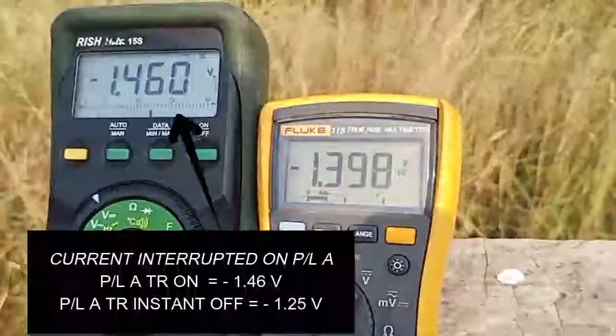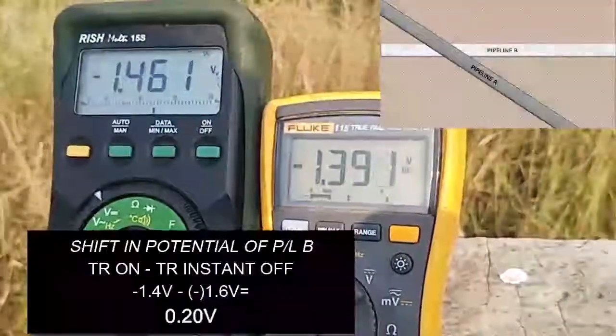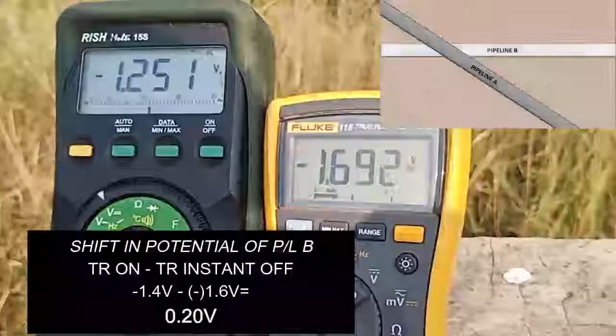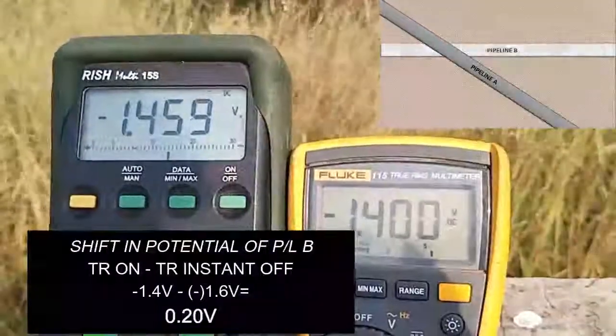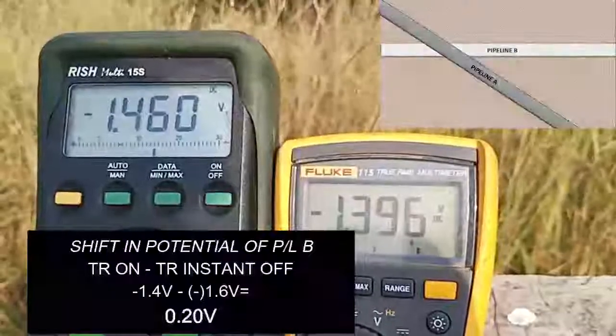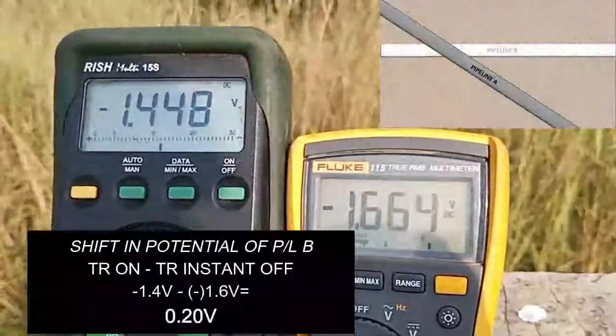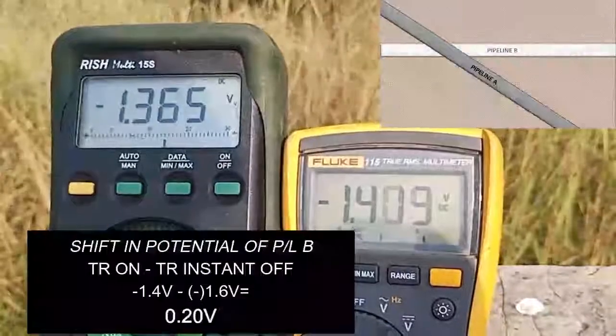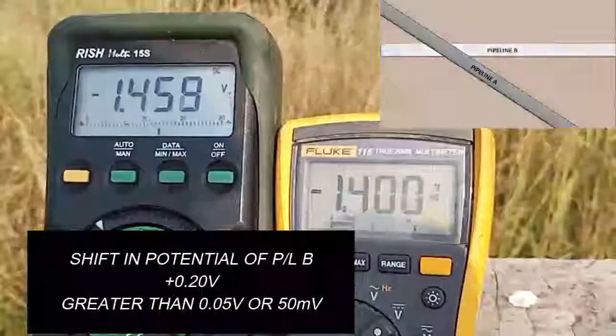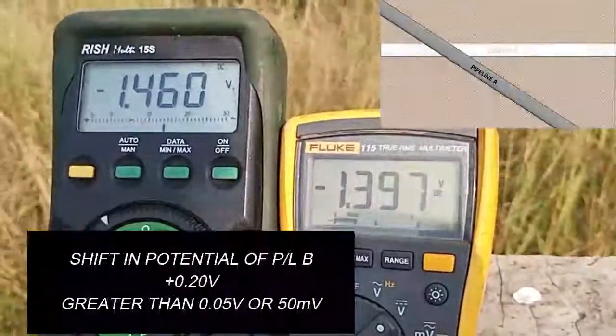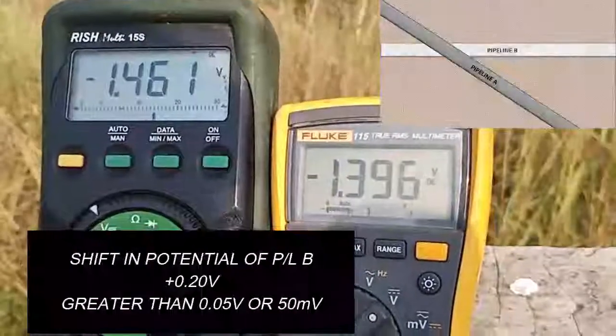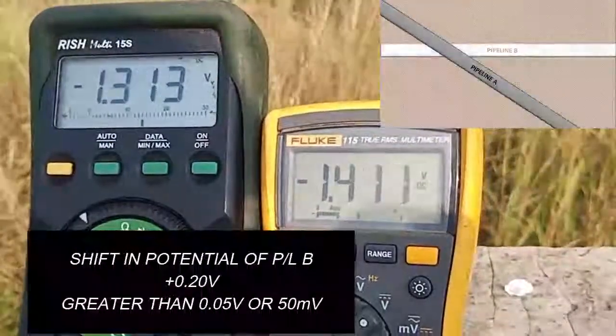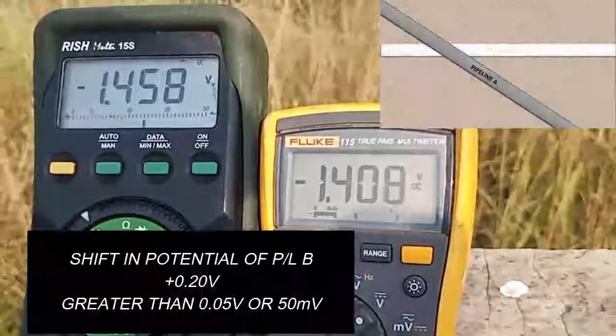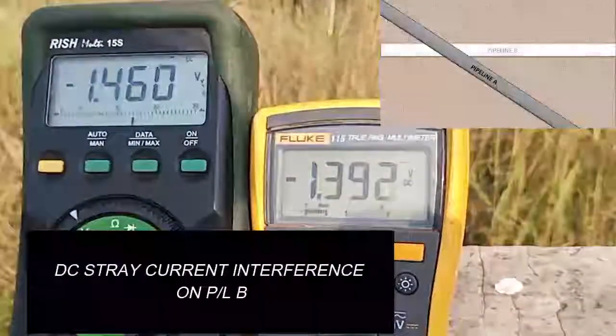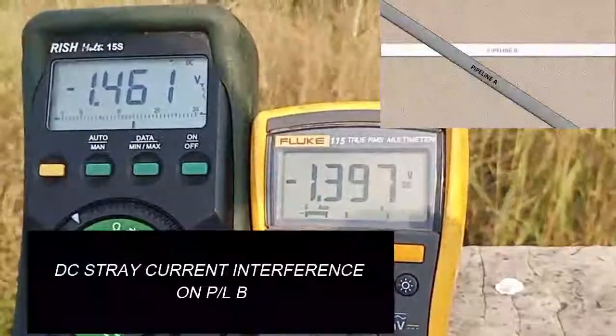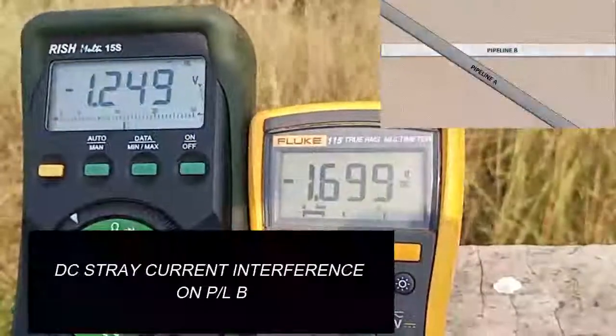The shift in the potential of Pipeline B is on potential minus the instant off potential, which is equivalent to positive 0.20 volts. There is a shift of potential which is greater than 50 millivolts on Pipeline B due to the interruption of Pipeline A's TR unit. This is a clear indication of DC stray current interference. Therefore, DC stray current interference on Pipeline B can be observed.